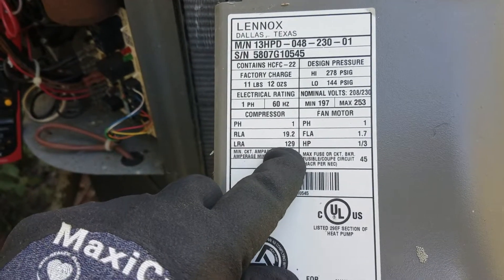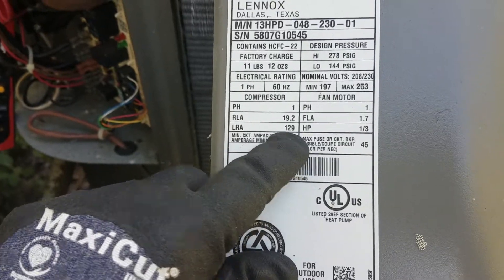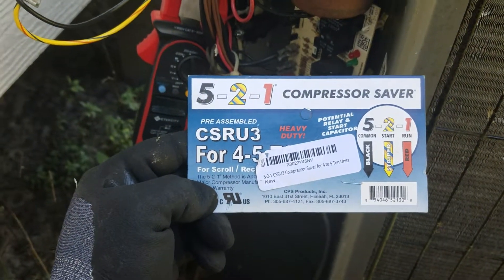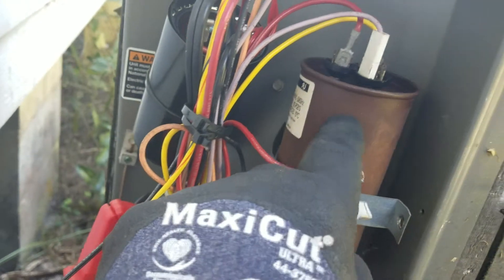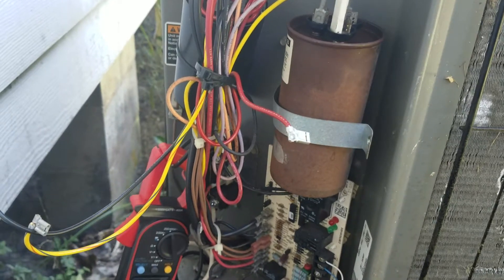My locked rotor amps is 129 - that's what it does when the compressor starts up. This 521 hard start kit, which I got off Amazon for $45, is supposed to assist the regular capacitor in here and hopefully cut it down in half.